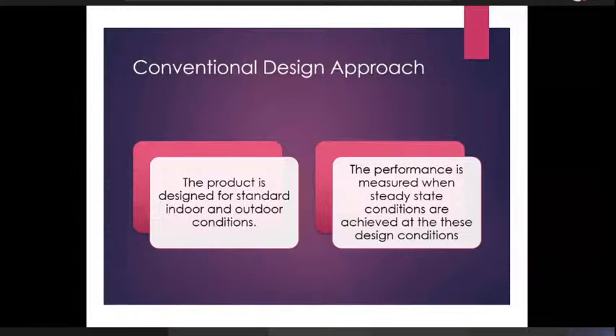So all that can be integrated into an analysis, and we reach a point where we can see a reasonable number, looking at temperature variations and conditions of part load, because of the customer's load being lower than what the unit is designed for. And the load also is a function of outside temperature, because when the outside temperature is less, the heat gain through the walls, the heat gain through the roof, the heat gain through infiltration, all of that also reduces.